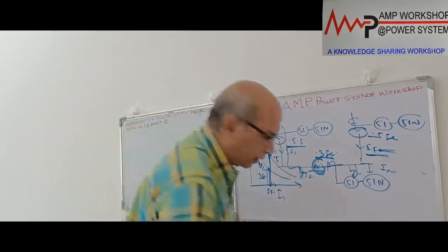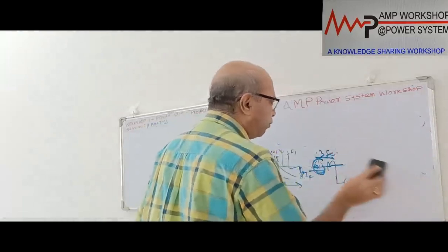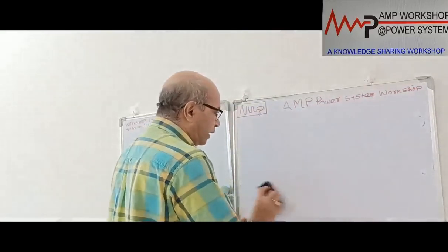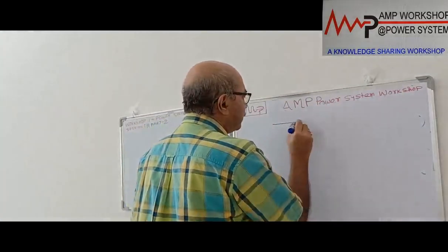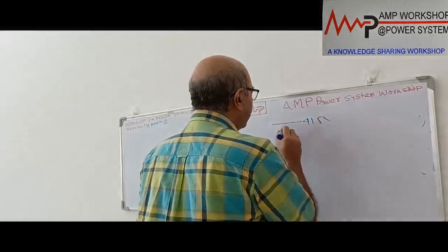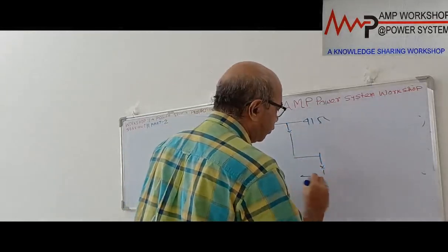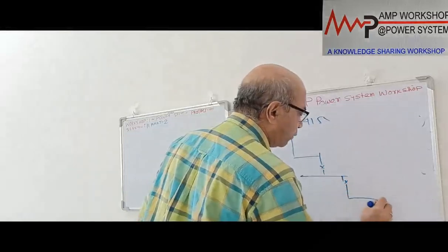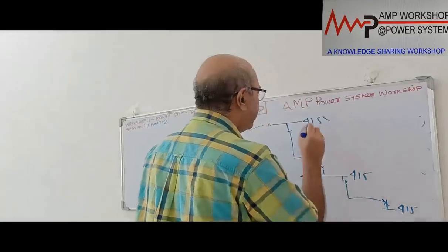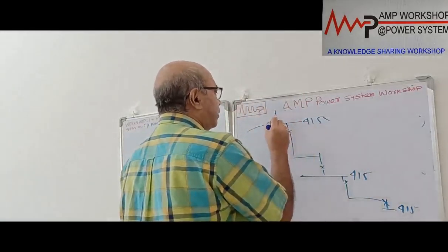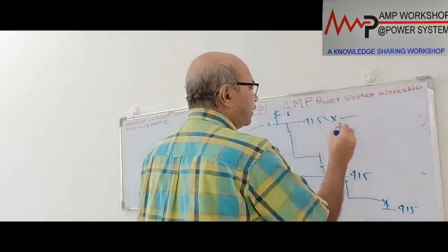But here is a problem. This is fine for one level. But if this switchboard is feeding power to another 415 volt switchboard, successively another two levels, then we have to look at it. We can accept 0.5 second, but suppose this is a 415 volt switchboard with a bus coupler, and there is a feeder over here going to another 415 volt switchgear. This is the third level. Here the incomer is coming over here, we are providing 0.5 second, and the bus coupler is operating at 0.3 second. In this case, fine.